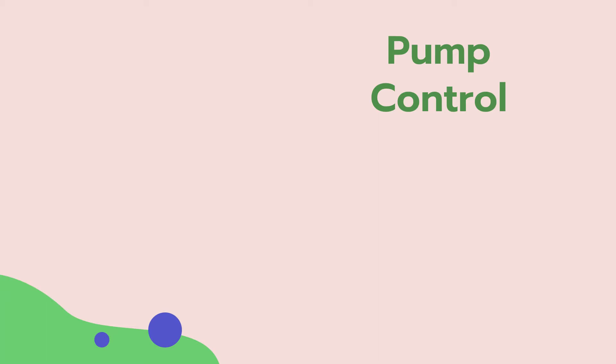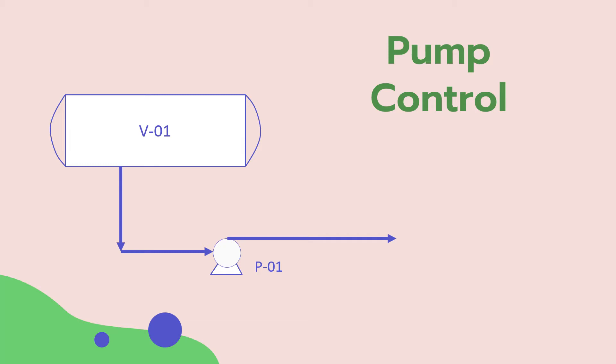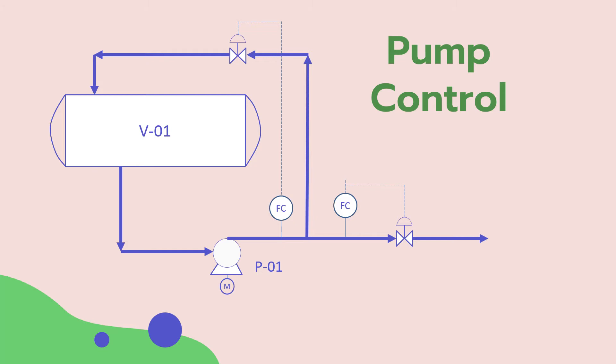The main control scheme is not developed in the P&ID, but it is determined when developing the process flow diagram or the PFD. The P&ID shall reflect this control scheme. Pump control has many different forms. We may use variable speed control to reduce the motor speed, hence changing the pump performance curve. Or the most common form can be through controlling the pump capacity by placing a control valve on pump discharge to control the system resistance. Also, in order to prevent operating the pump at more than minimum flow, we would need to add a minimum flow control, which can have different forms as well. If you want to know more about pump calculations, performance curve, and control schemes, you can check out the link in the description.